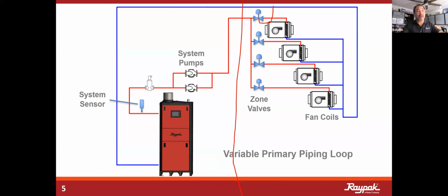The other thing that plays into that is, where is this sensor located? If that sensor isn't located close enough to the outlet of the heaters, if it's located a little further down the line and it's calling for heat, and there's lower flow, that's going to also impact the way that heater operates. So, you kind of get where I'm going with this.